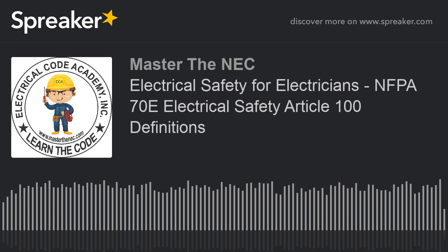Obviously, hazard: a source of possible injury or damage to health. Hazardous: involving exposure to at least one hazard. If it's at least one hazard, then it's hazardous. Okay. Incident energy. You've heard me use that term, incident energy, right there. What is it? Incident energy is the amount of thermal energy impressed on a surface a certain distance from the source, generated during an electrical arc event.